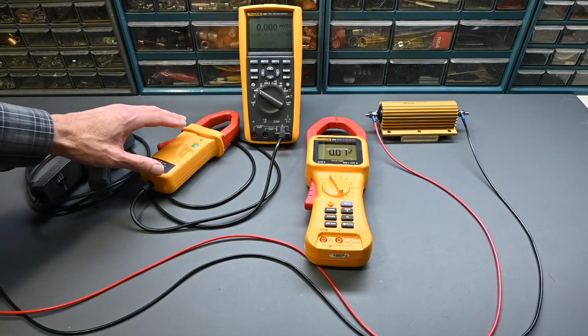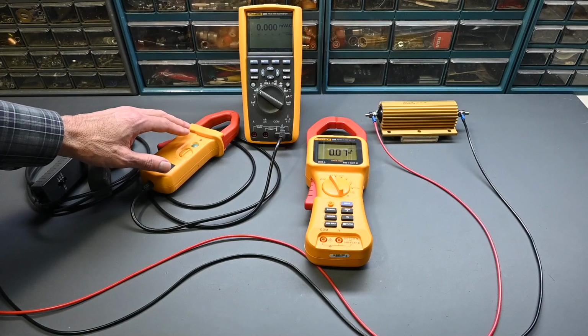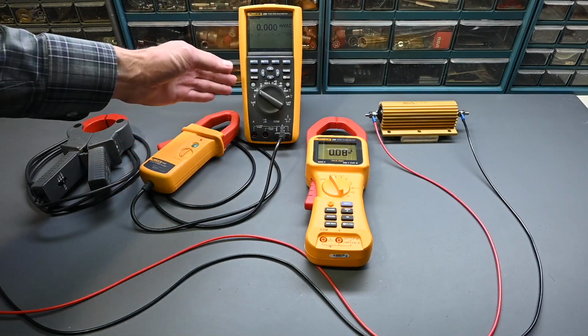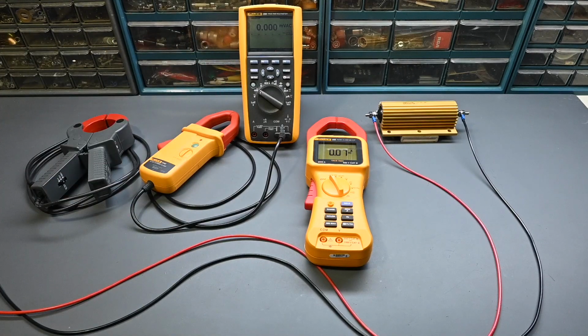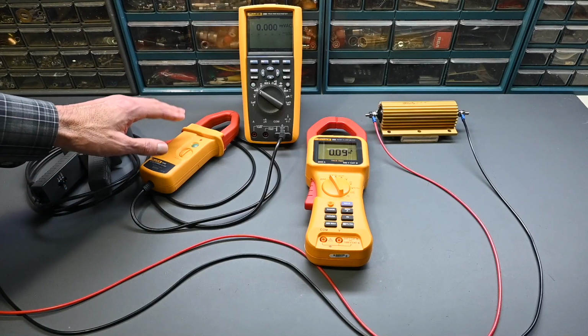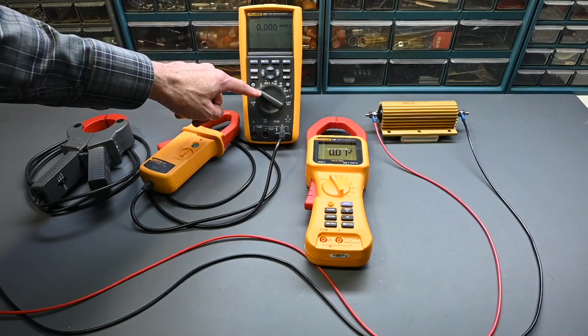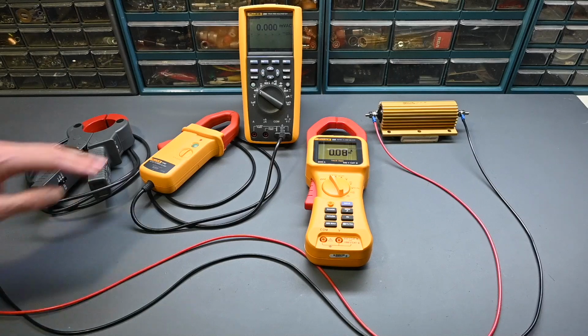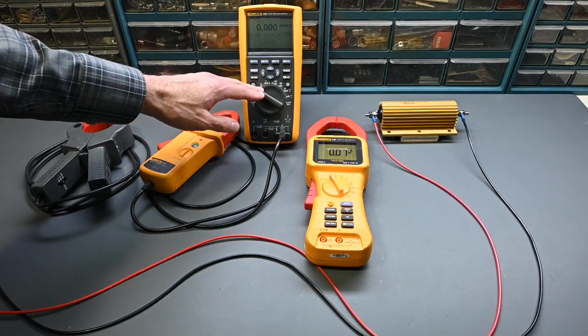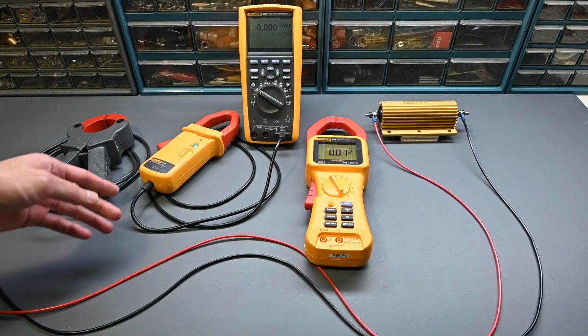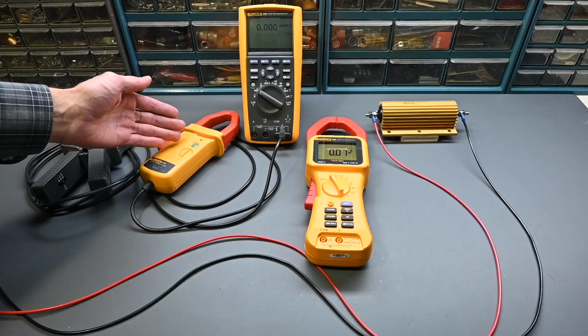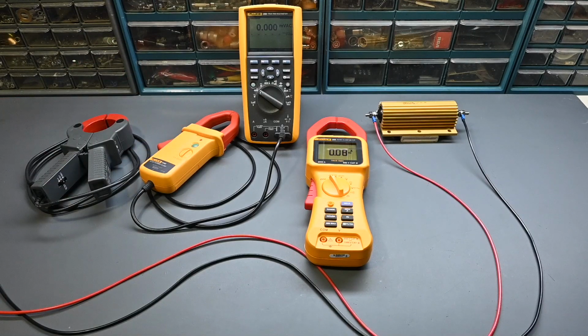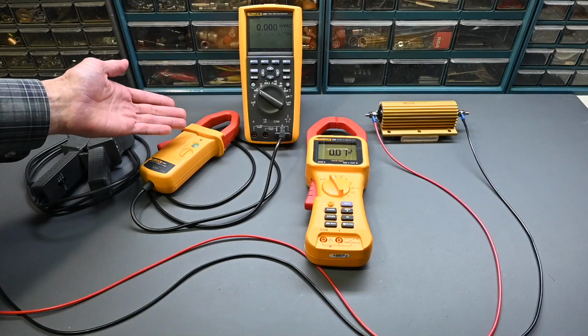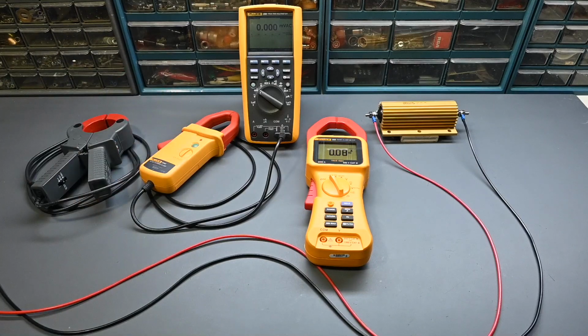Now a current clamp like this Fluke i410 can measure both AC and DC current, but it requires an external digital multimeter to take the reading. If you're measuring AC current, then this needs to be set to AC volts, or millivolts for that matter. And if you're measuring DC current, then this needs to be on DC millivolts. Basically the signal that's coming out of here is either AC voltage or DC voltage, depending on the current that you're measuring. There's no switch to select between AC and DC. It's just up to you to know which type of current you're measuring, and then make sure to have the meter selected appropriately.